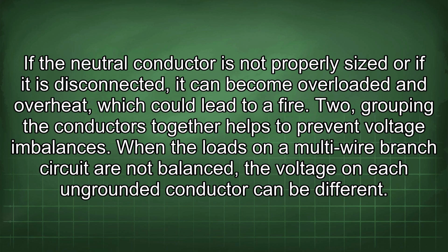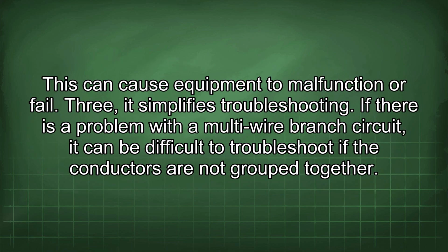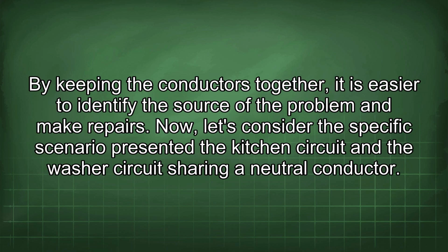2. Grouping the conductors together helps to prevent voltage imbalances. When the loads on a multi-wire branch circuit are not balanced, the voltage on each ungrounded conductor can be different. This can cause equipment to malfunction or fail. 3. It simplifies troubleshooting. If there is a problem with a multi-wire branch circuit, it can be difficult to troubleshoot if the conductors are not grouped together. By keeping the conductors together, it is easier to identify the source of the problem and make repairs.